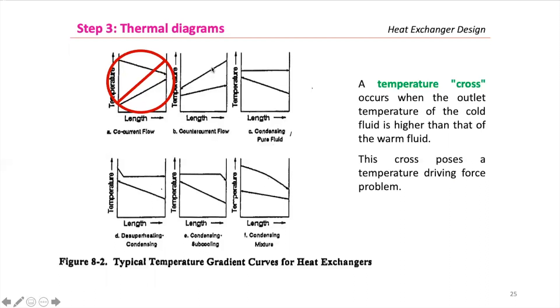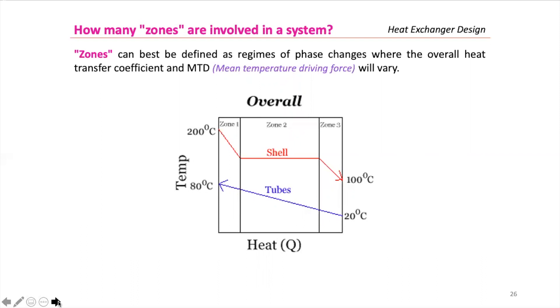We start from the cold end to the hot end, and what we want to avoid in these thermal diagrams are temperature crosses — because that occurs when the outlet temperature of the cold fluid is higher than that of the warm fluid. That means we are doing something really wrong, because this will pose a temperature driving force problem. All of the other cases are correct, and this is how a cross would look like.